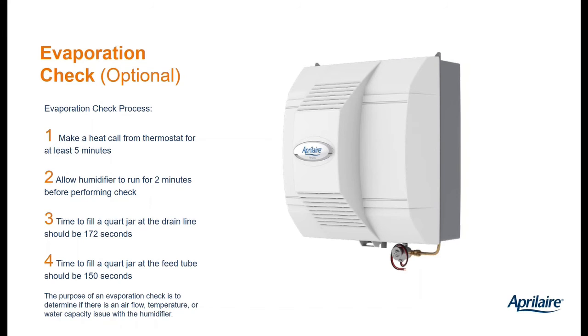Then you're going to take the cover off the humidifier. You're going to disconnect the feed tube and have the feed tube run into the quart jar. As soon as that first drop of water goes into the quart jar, you're going to start the timing. You're going to time how long it takes to fill the quart jar from the feed tube. Jot down that time.